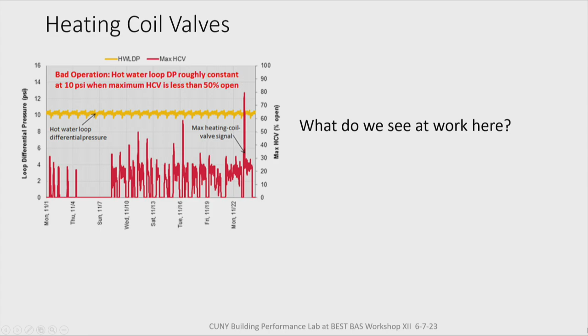So here's what we'd prefer to see. We've lowered the loop differential pressure, which forces the valve to open up. The whole system works at a lower differential pressure and pumps less hard. As the valve opens, the VSD may speed up a little, but the lower differential pressure will allow the pump to spend even more time working at a lower speed.